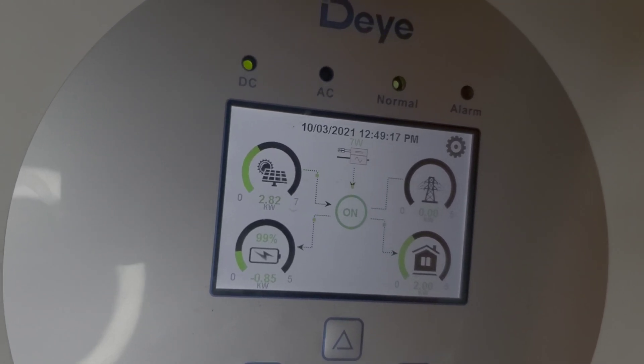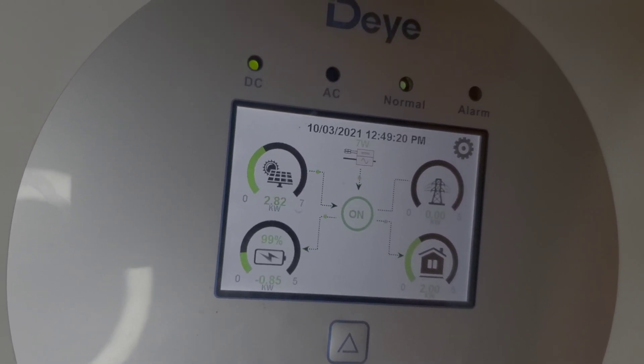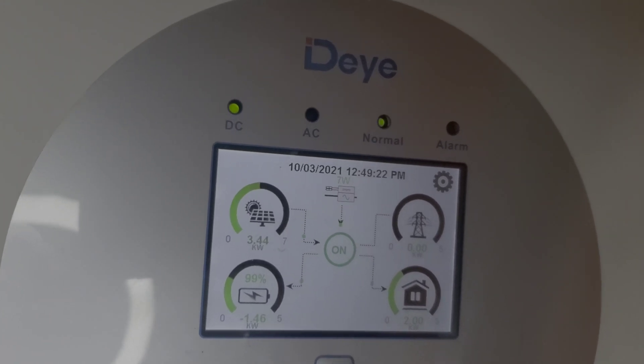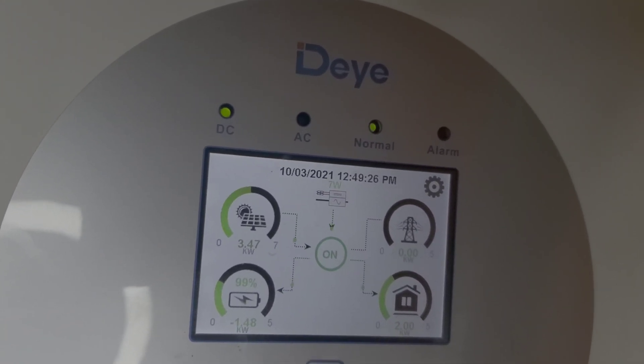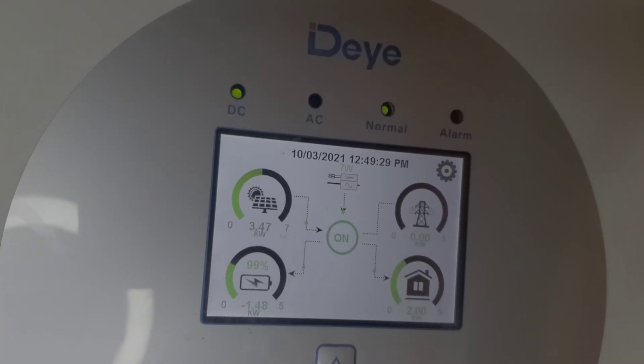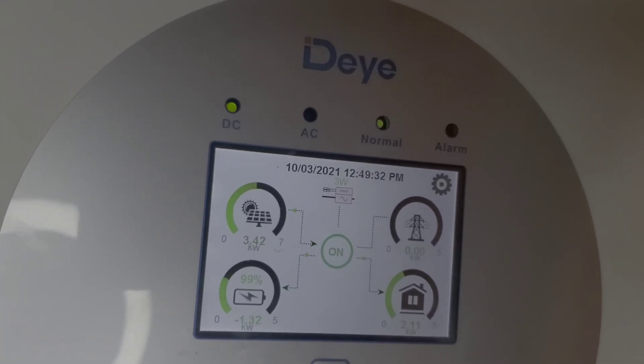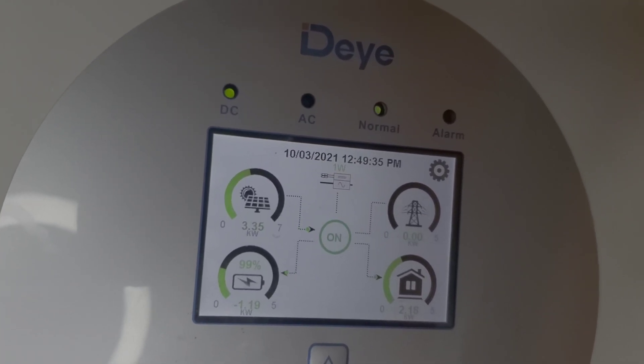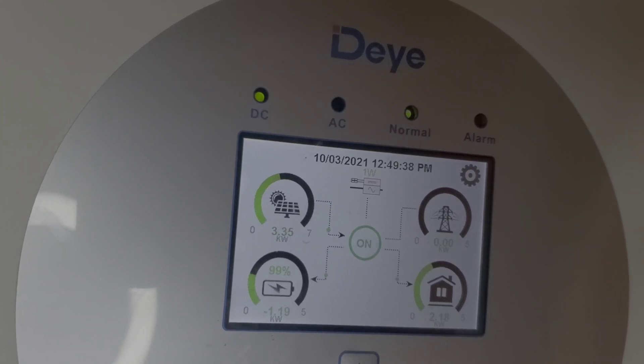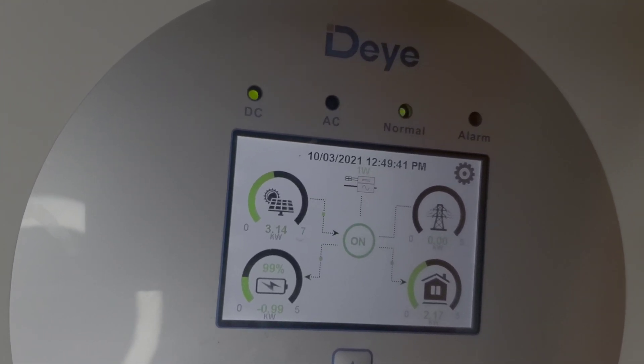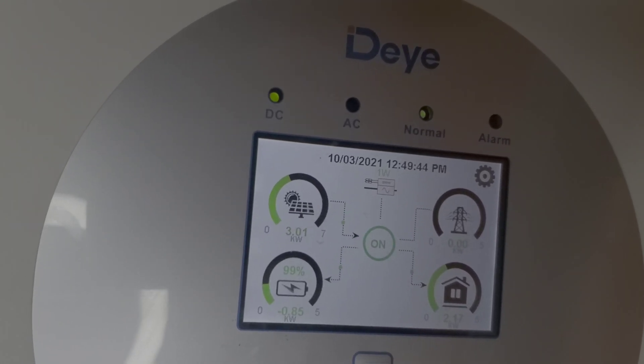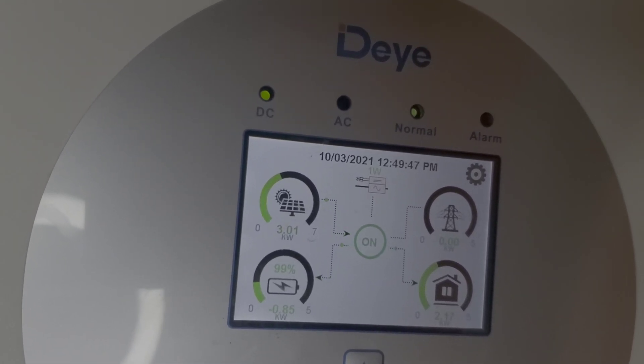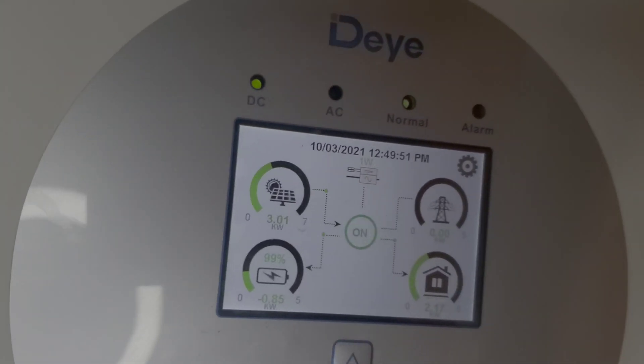And the way it does it is by shifting frequency. So it could alter the frequency. It could go from as little as 49.9 all the way to 54 point something which you saw outside. And at 54 point something, the PV inverter goes silent. It goes into standby, is on standby until the battery percentage drops to 95%. Then the frequency goes back to 49.9 to 50 hertz, and then that inverter starts sending juice back to this one.